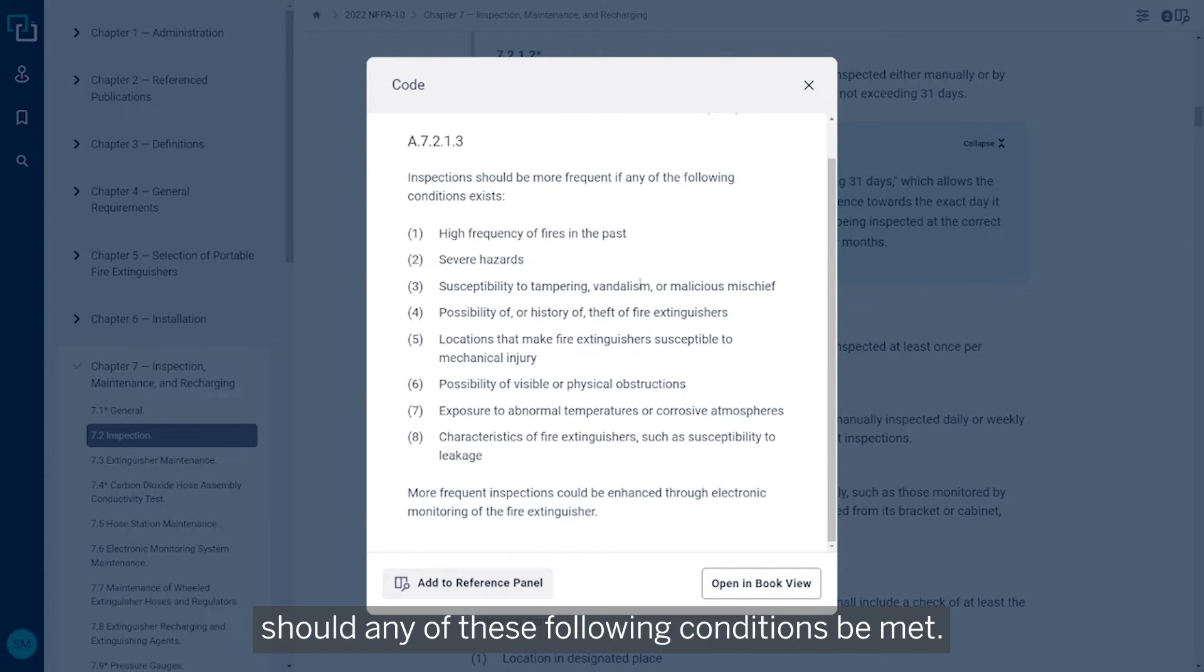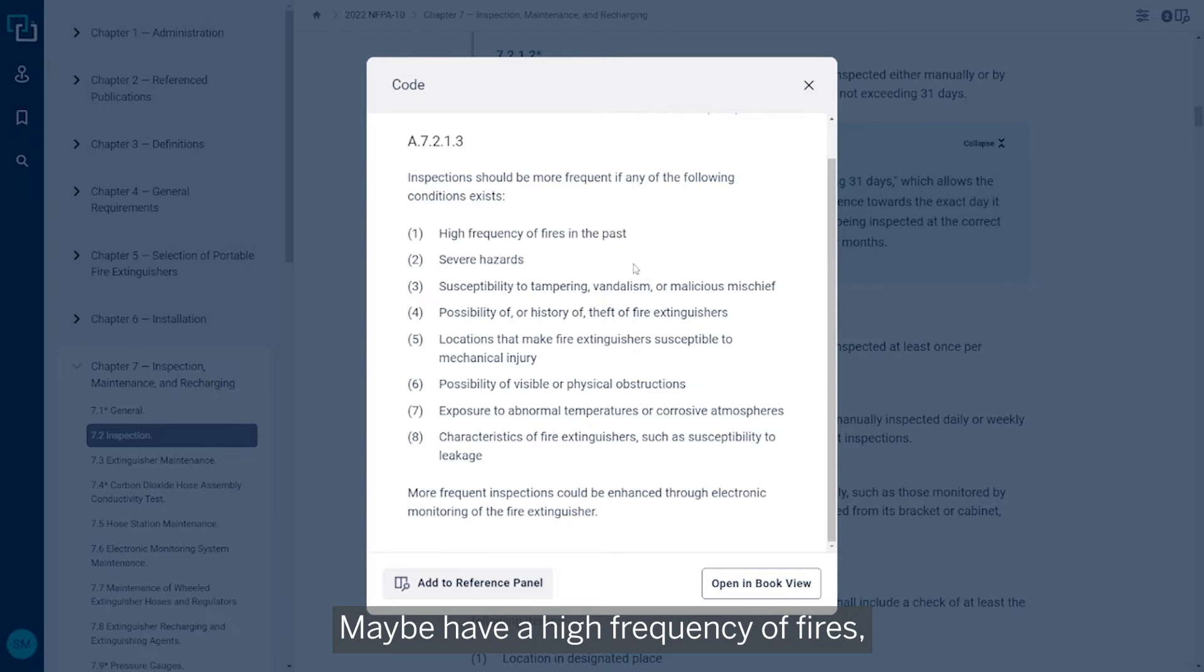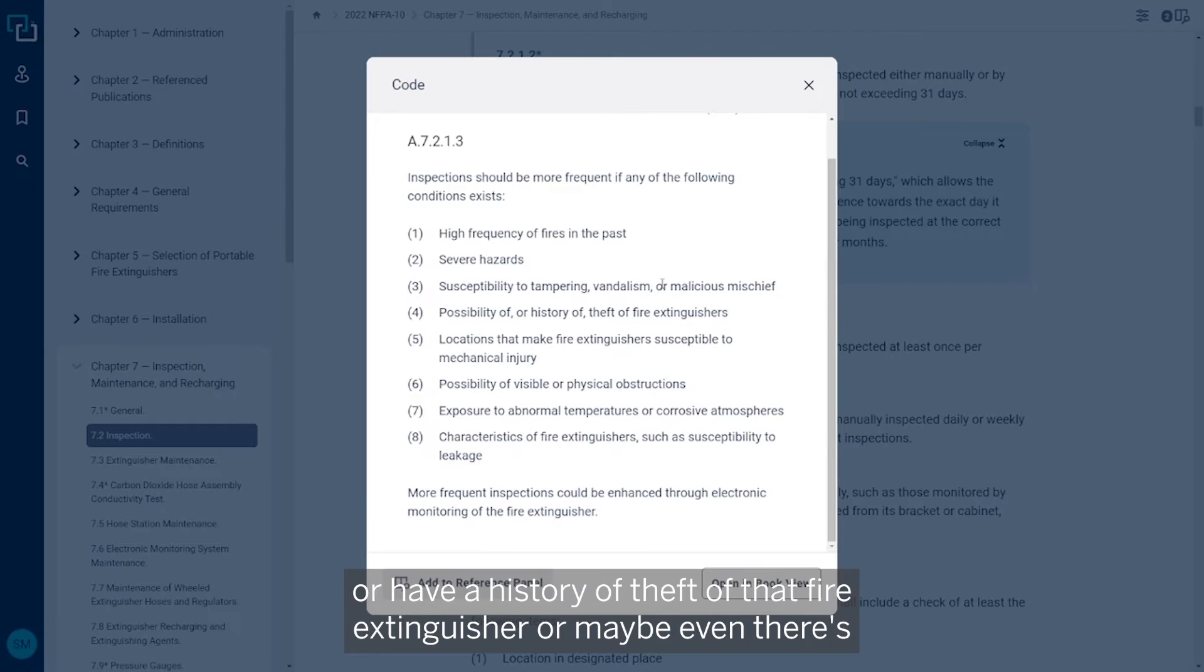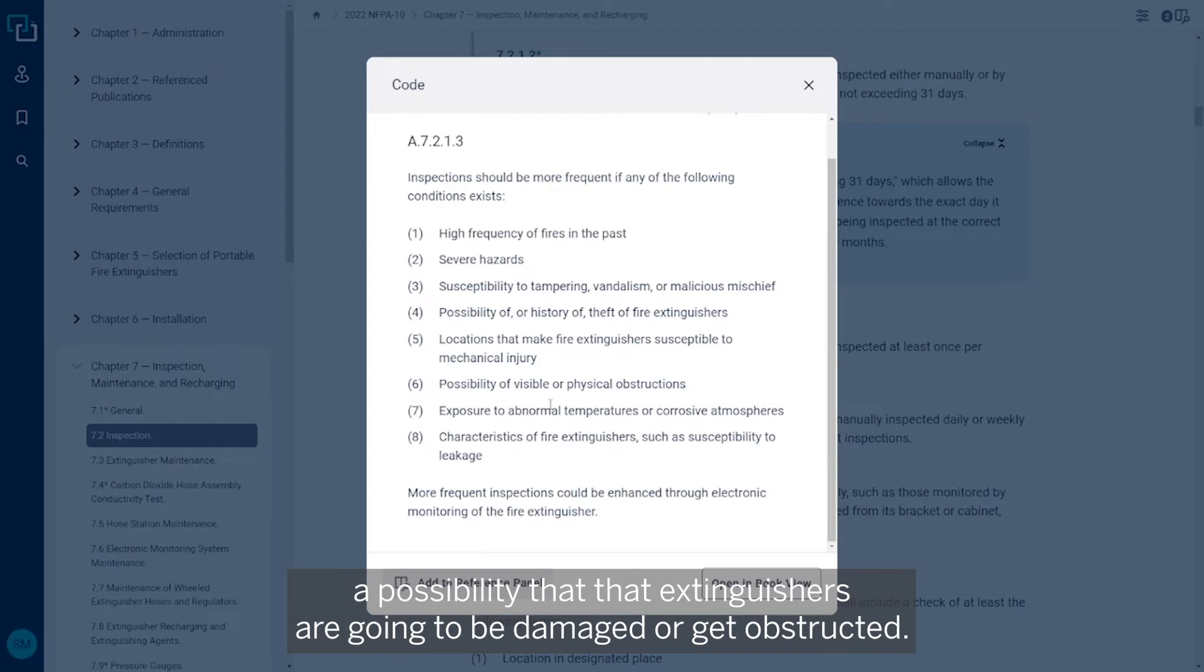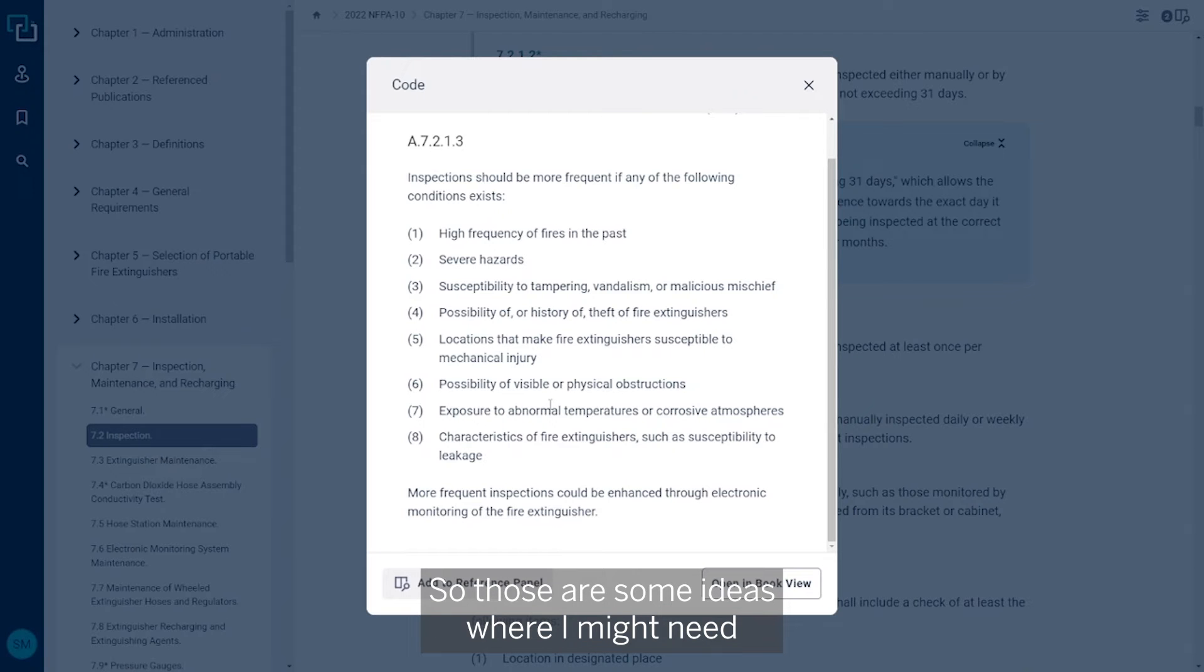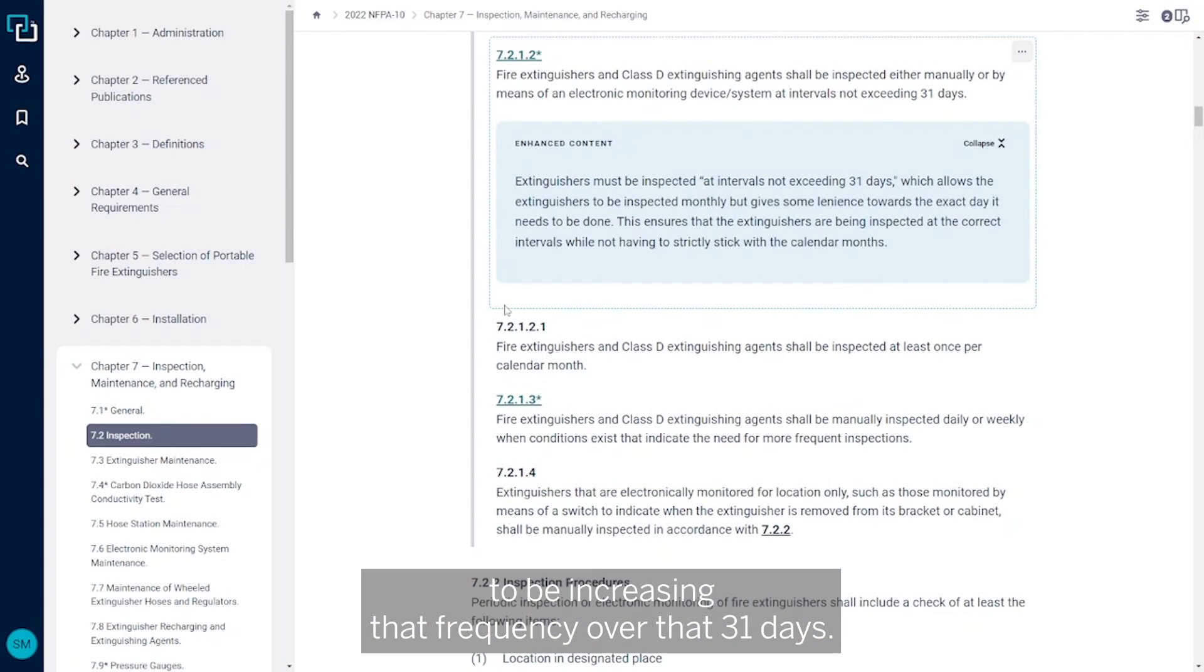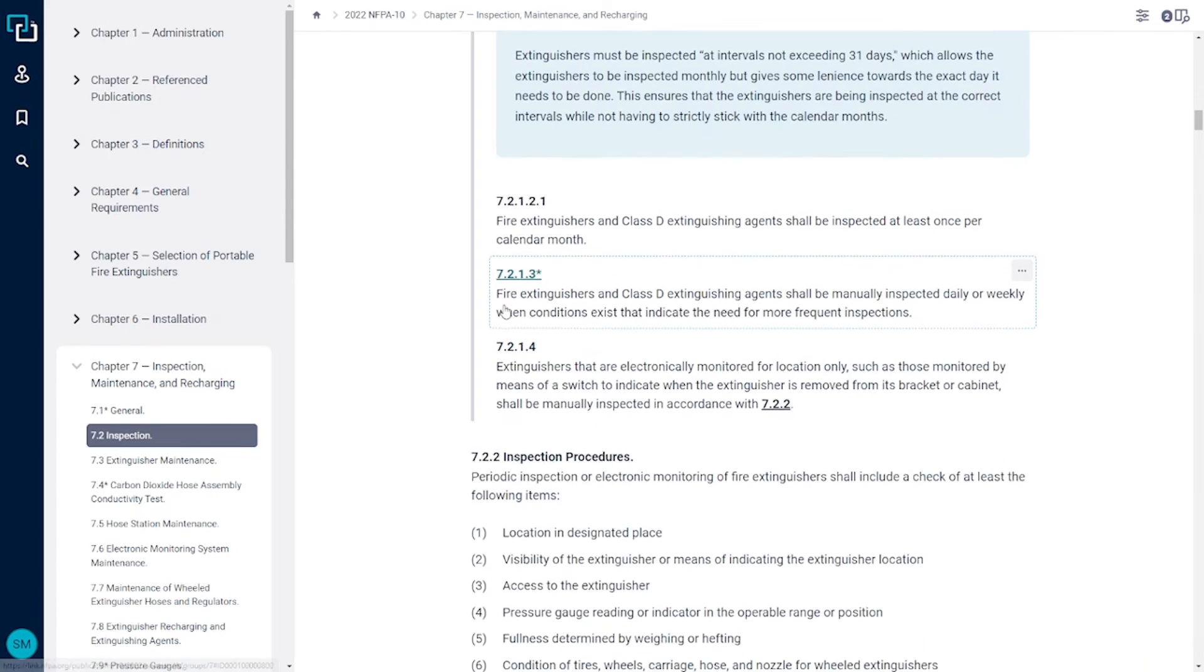Maybe I have a high frequency of fires. Maybe I'm susceptible to tampering or vandalism, or I have a history of theft of that fire extinguisher, or maybe even there's a possibility that that extinguisher is going to be damaged or get obstructed. So those are some ideas where I might need to be increasing that frequency over that 31 days.